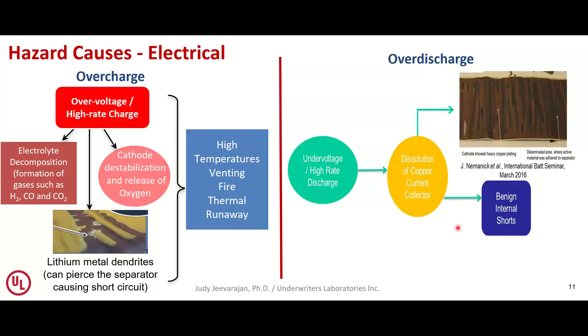This gas production can be visibly observed as swelling in pouch cells, but not in metallic can cells. All these factors together can eventually cause the cell to go into thermal runaway, even without an overcharge condition or exceeding the manufacturer's upper charge limit. This hazard cause had been overlooked quite a bit in the past, but people are now realizing there are more hazards associated with it, and they've become more vigilant. This leads into external short circuit.